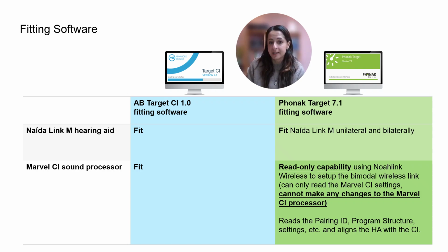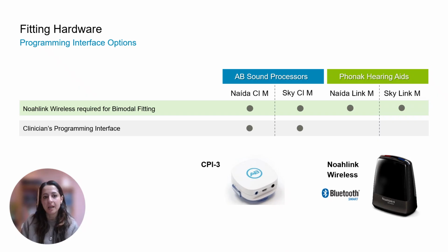The cochlear implant is connected as read-only, so don't worry about accidentally making any changes to this, but this means that the information about the programs and the settings can be automatically pulled through to align the hearing aid accordingly. The hearing instruments connect to the Noahlink Wireless using Bluetooth Low Energy, which allows for wireless fitting while at the same time conserving battery life.